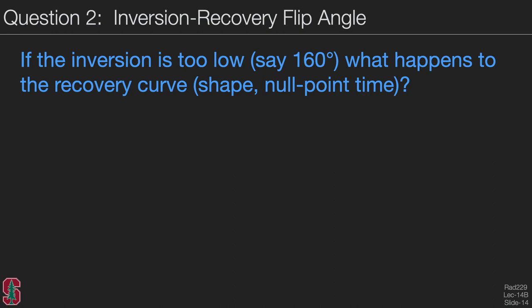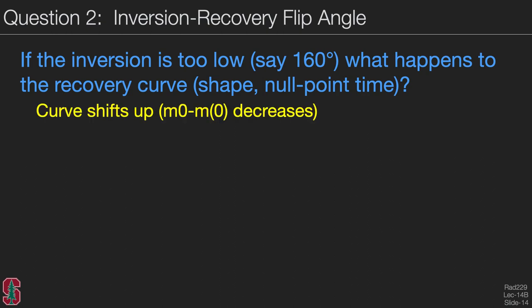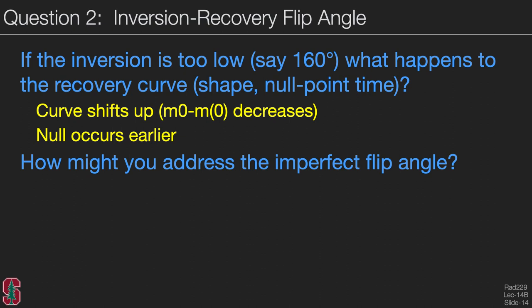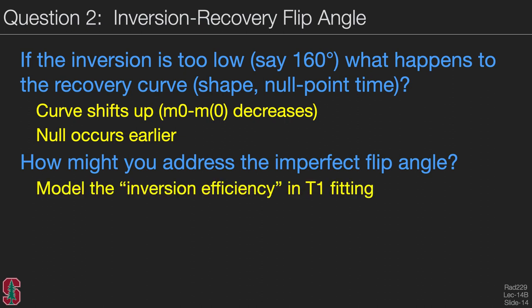For the inversion recovery question: what happens if the inversion has too low a flip angle? The recovery curve shifts upward, so the null point is reached quicker because the difference between equilibrium magnetization and starting magnetization decreases—the null occurs earlier. To address this imperfect flip angle, if you're doing T1 fitting by measuring points along the curve, you can model the inversion efficiency or flip angle in the T1 fitting. Alternatively, you can use adiabatic inversion pulses, which are better at achieving full inversion in the presence of B1 transmit variation.